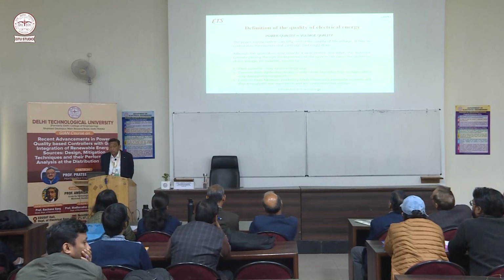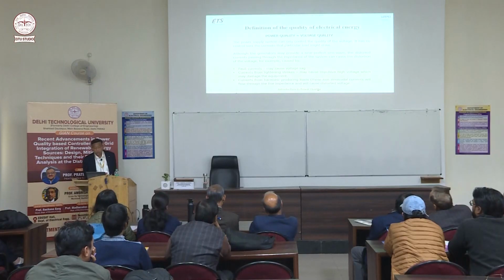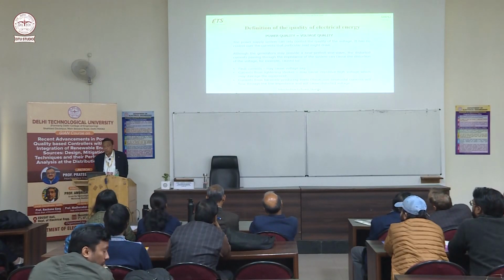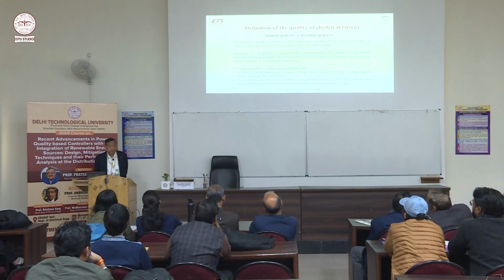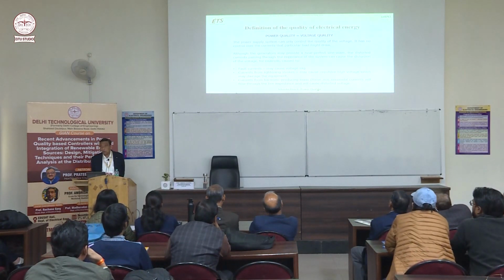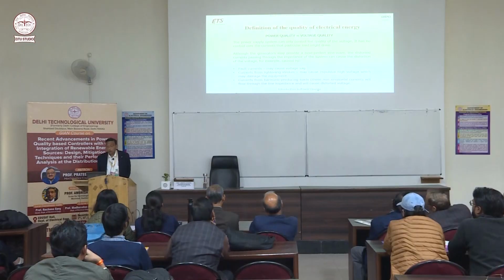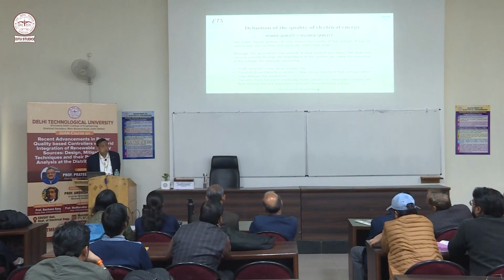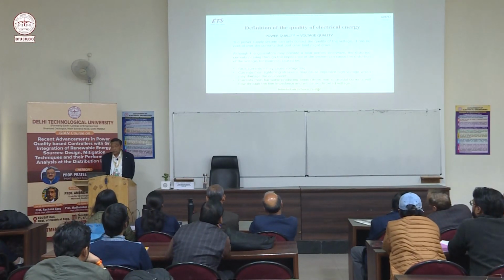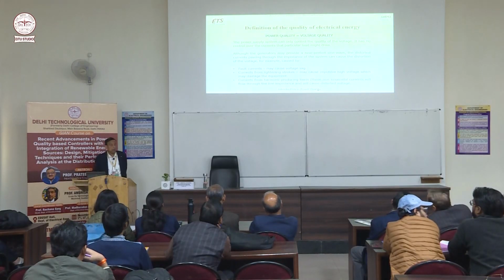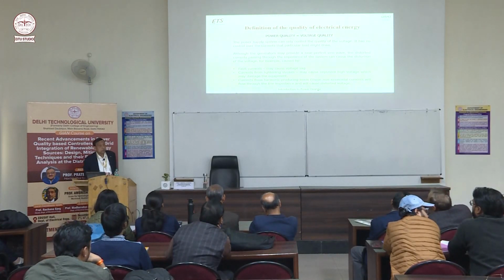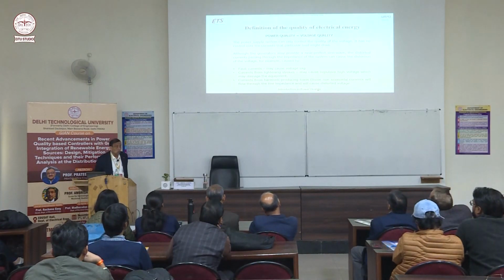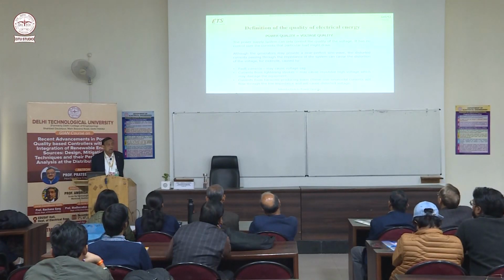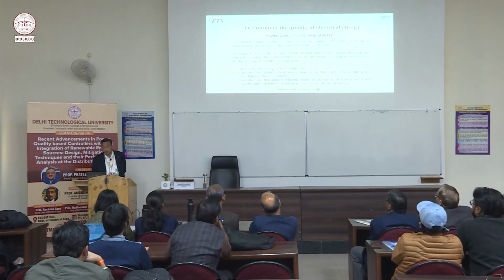Like a lightning stroke: if there is a thunderstorm, a lightning stroke may cause an impulsive high voltage which may damage equipment, like your transformer may be burned down, right? Then currents from harmonic producing loads. These non-sinusoidal currents flow through the impedance of the line, which will cause a distorted voltage drop. And finally, at the PCC, the point of common coupling, you may have distorted voltage.